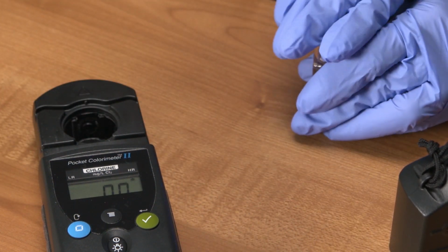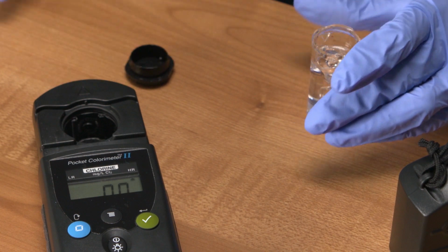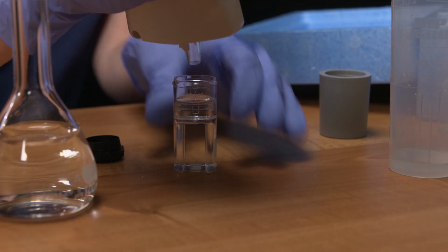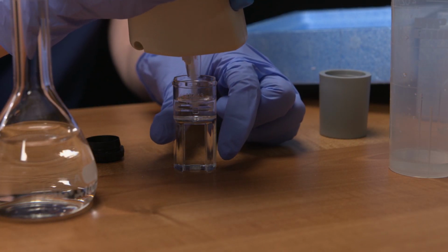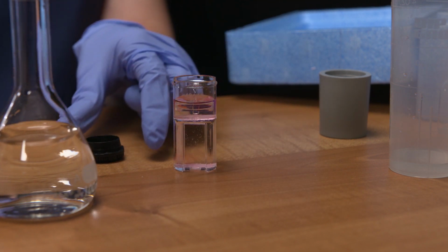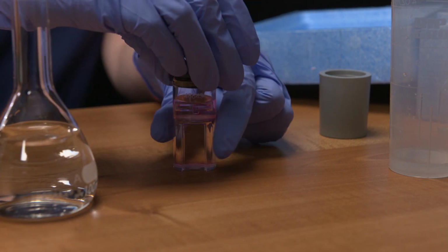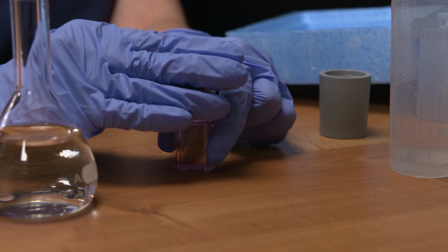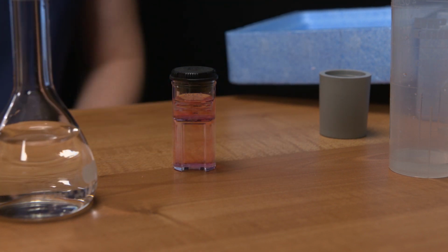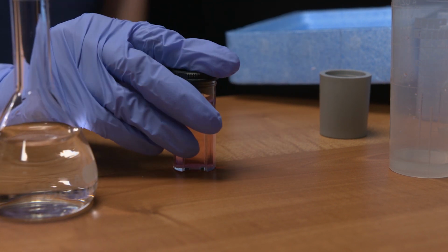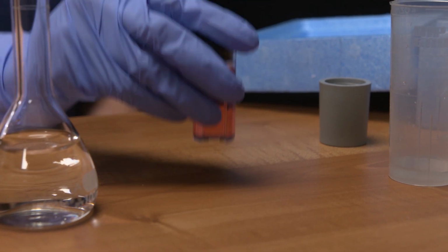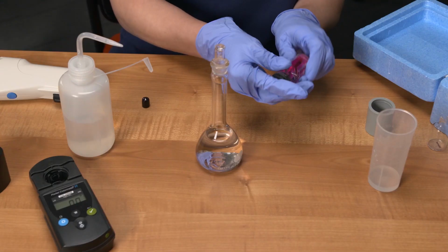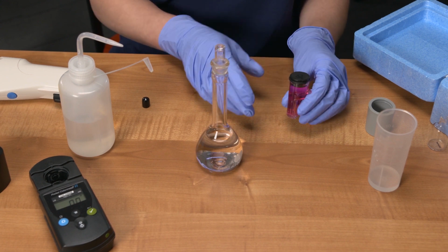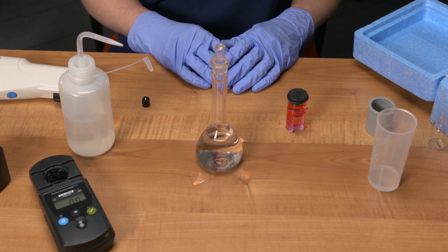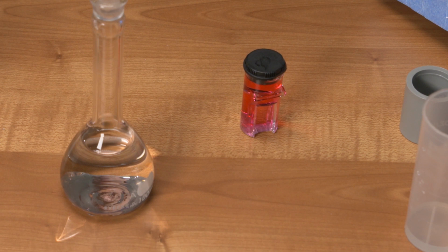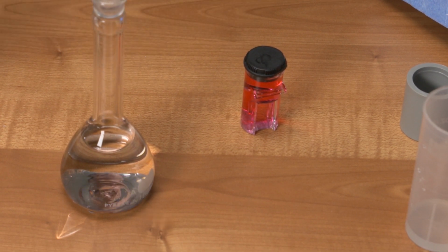We can use DPD reagents for either free or total chlorine because both of these reagents can measure the free chlorine in our standard. You should select free or total based on the type of disinfectant residual that you have. If we were measuring in a water system using chloramine in the distribution system, we would need to measure for total chlorine. Now we mix our reagent. We do this by gently inverting the vial with the cap on. We don't want to shake it too vigorously, or we could cause air bubbles.